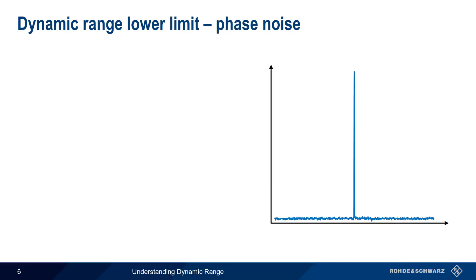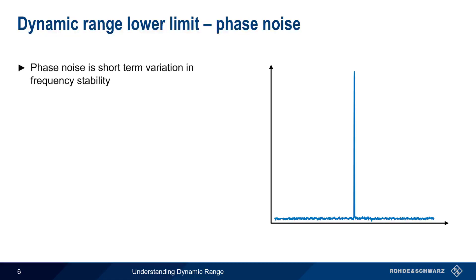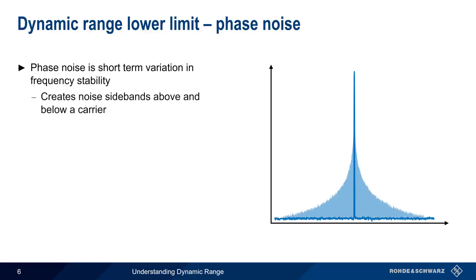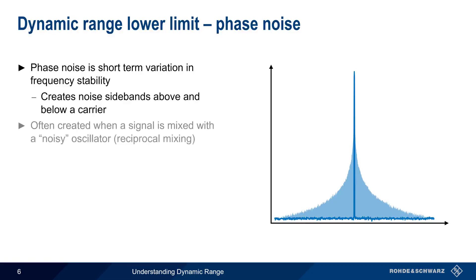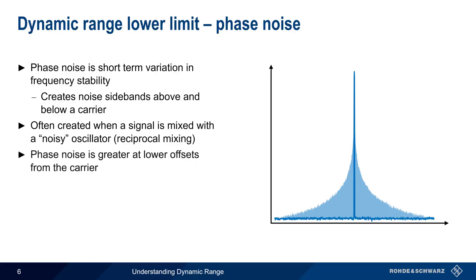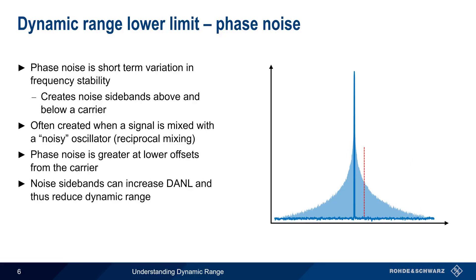Phase noise sometimes also contributes to the lower limit of dynamic range. Phase noise is short-term variation in the frequency stability of a signal. This instability creates noise in the form of sidebands both above and below a carrier. In many cases, this phase noise is created by the mixing of an input signal with a noisy oscillator, and this is often called reciprocal mixing. Phase noise is usually greater the closer you are to the carrier. The noise power in these phase noise sidebands can also increase DANL, and thus the presence of phase noise can sometimes reduce an analyzer's dynamic range.